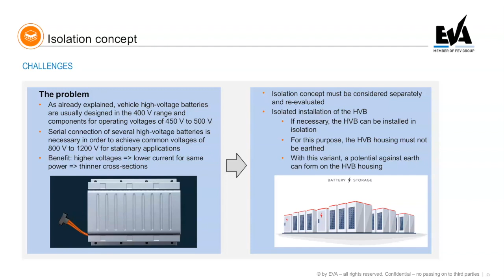So let's have a look. What can you do with the isolation? The isolation concept must be considered separately and re-evaluated. This is quite easy to understand. You cannot use it because of the different voltage range, and there's one solution: you can install the high voltage battery in an isolated way. For this purpose, the high voltage battery housing must not be earthed. But on the other hand, with this variant, there are potentials against earth that can form on the high voltage battery housing. This means you have to consider this in the whole isolation and safety concept. So that's it for the isolation concept.